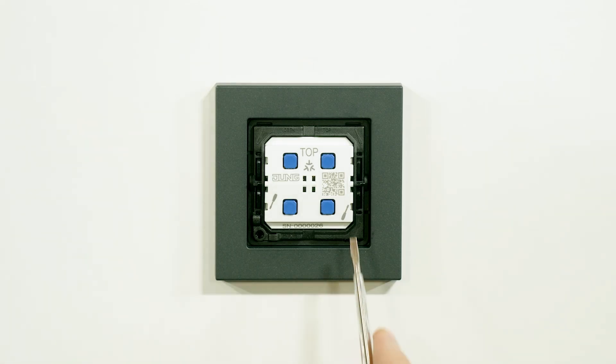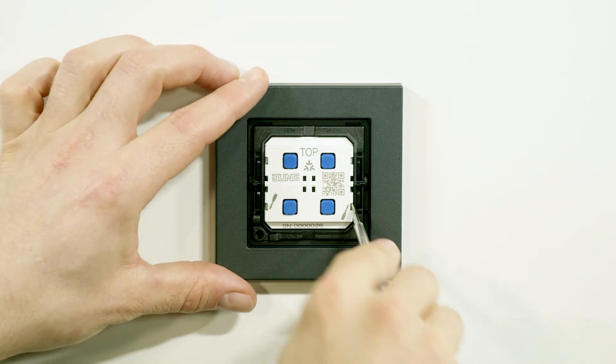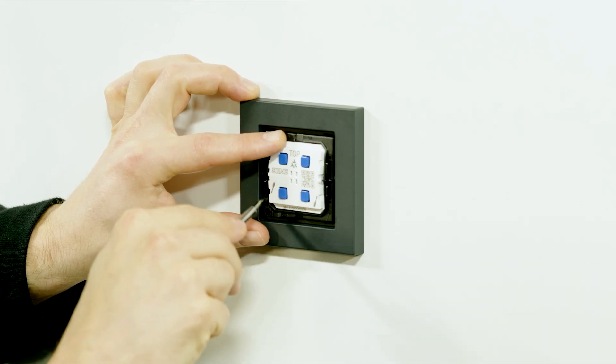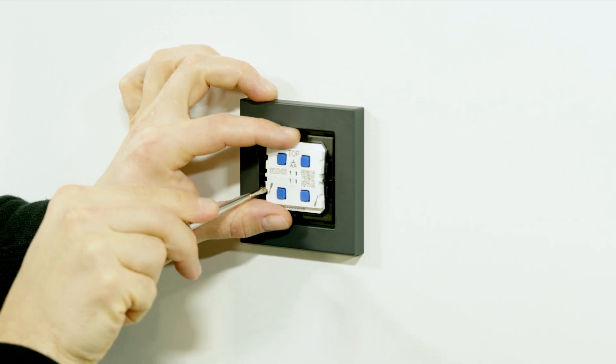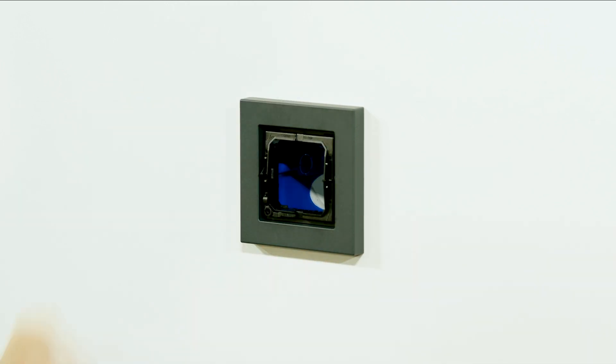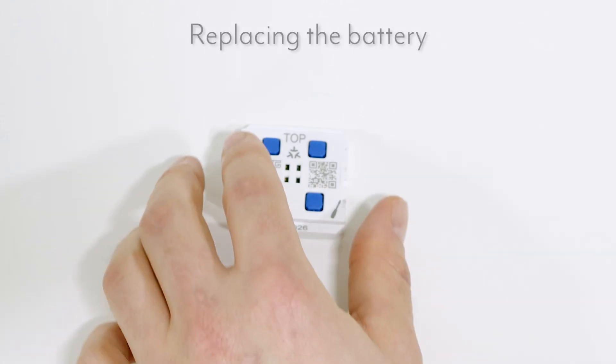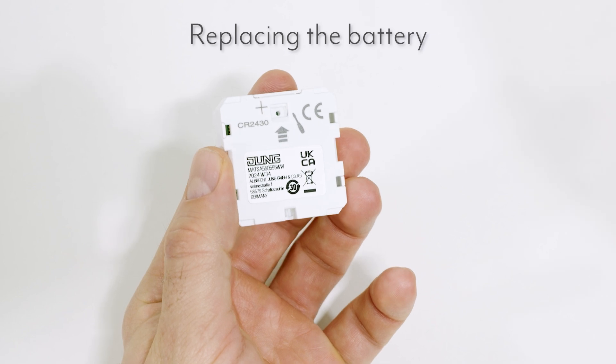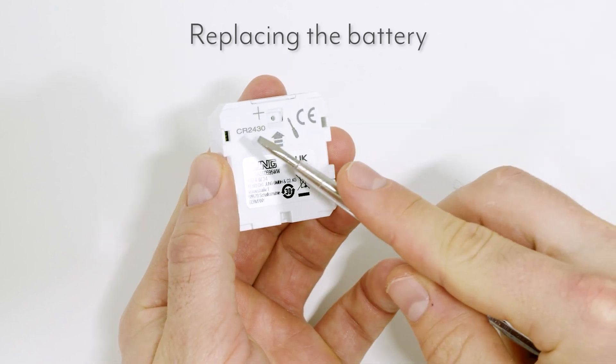Then carefully lever the radio module from the mounting ring. To do this, use a flat blade screwdriver with a blade width of 3 mm or less to reach into the two outlets on the module and remove it from the mounting adapter. The META push button has a CR2430 lithium button cell battery.